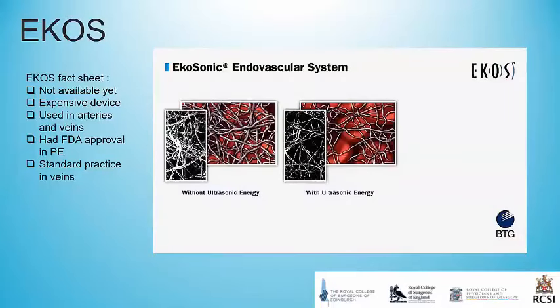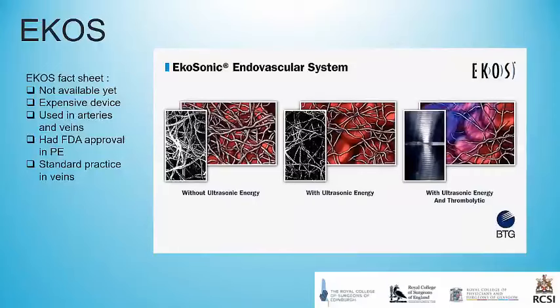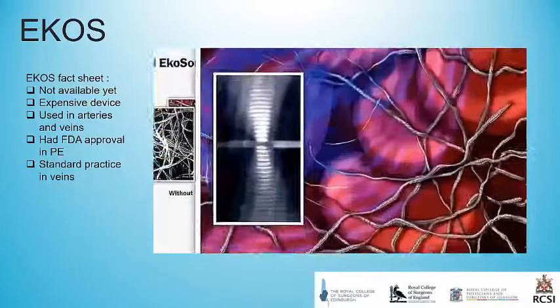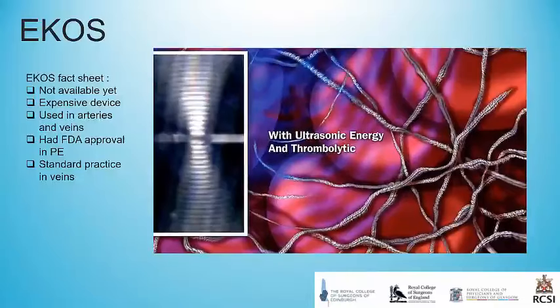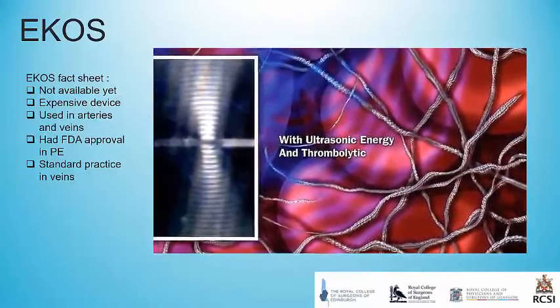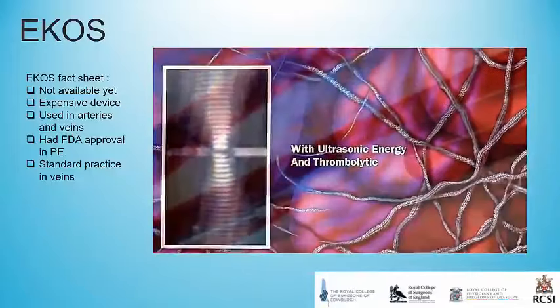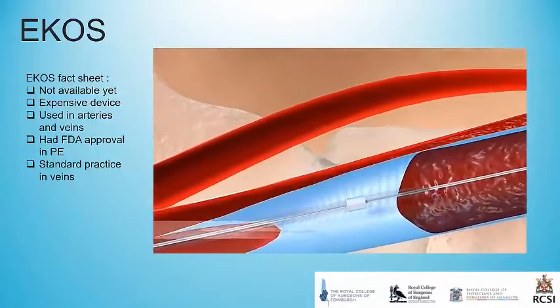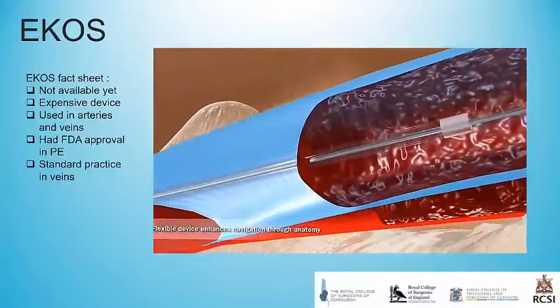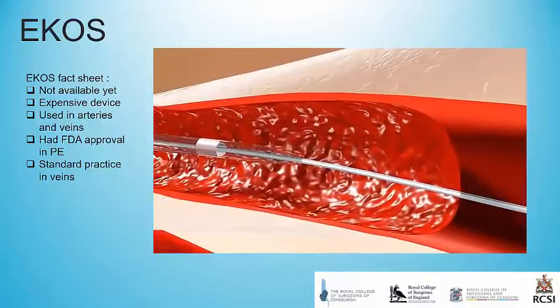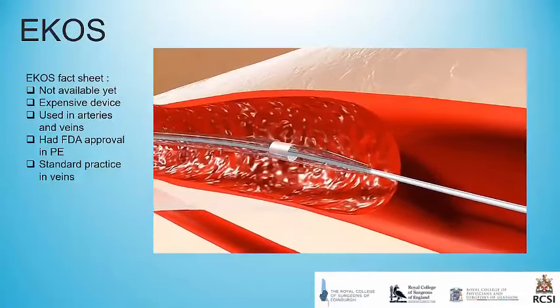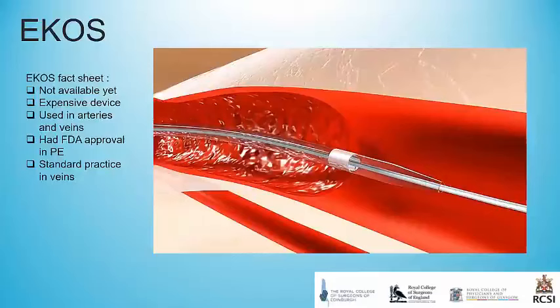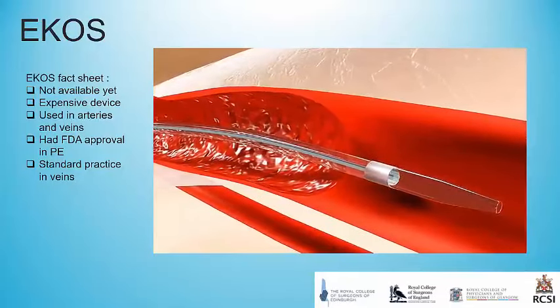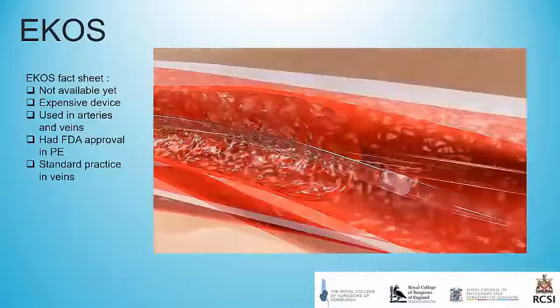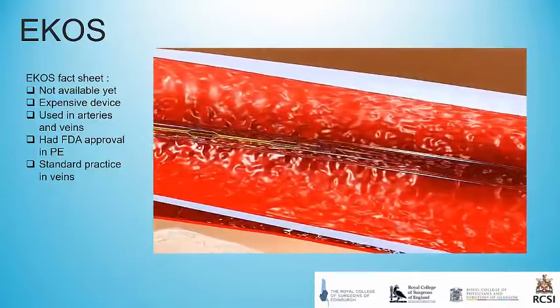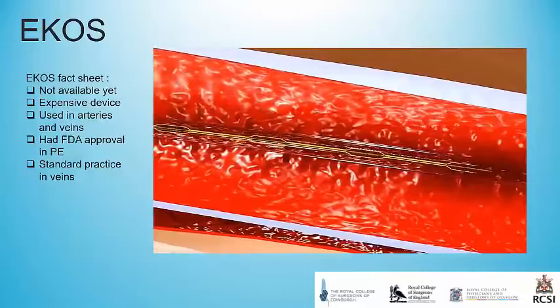It simultaneously delivers both the lytic drug and ultrasound energy to the clot. Together, they quickly dissolve the clot and restore blood flow, without causing hemolysis or vessel and valve damage. Advance the EkoSonic infusion catheter over the guide wire and across the treatment site. Note that radiopaque marker bands at each end enhance catheter visibility. Remove the guide wire and the infusion catheter is ready to receive the ultrasonic core. Gently insert the ultrasonic core within the treatment zone of the infusion catheter until the luer fittings can be locked.